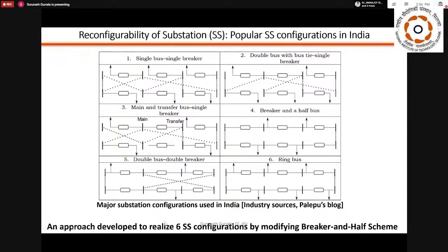There is something called double bus double breakers. Predominantly in the country, what we see on all generating stations is either main and transfer bus or double main transfer bus. So these are the two you will see. In distribution systems and breaker and half is predominantly used in very high voltage substations like 765 and 1200, where you need extreme reliability. Here, for one feeder, you will have two dedicated breakers, and there will be two buses supplying or energized at any point. Ring bus is a configuration which is used when high reliability is needed and multiple feeding points are there.